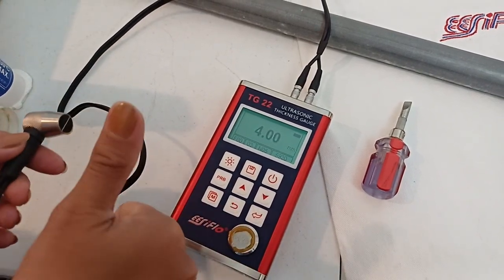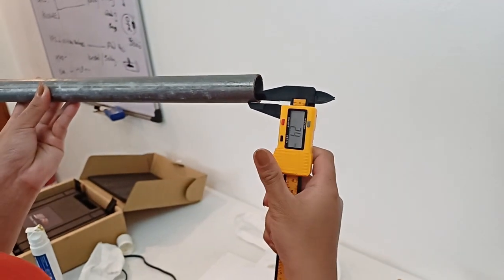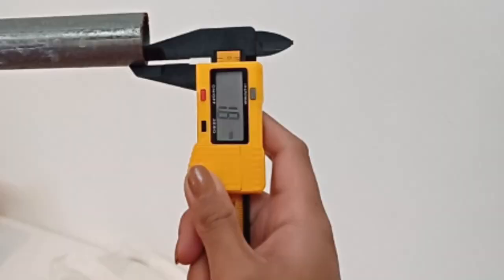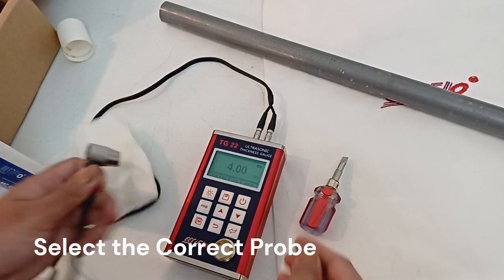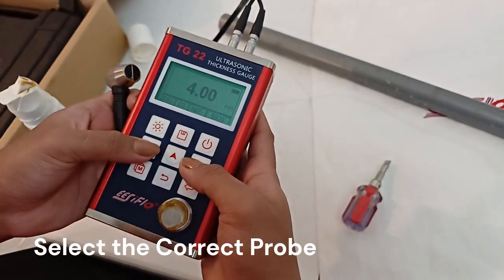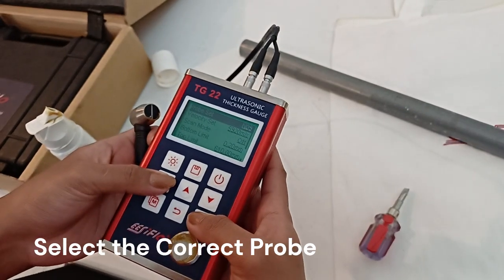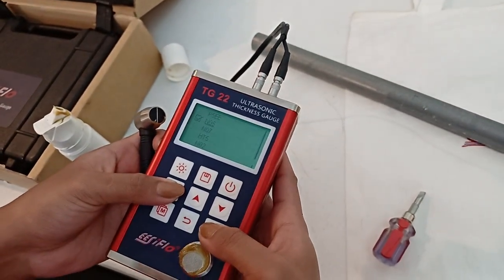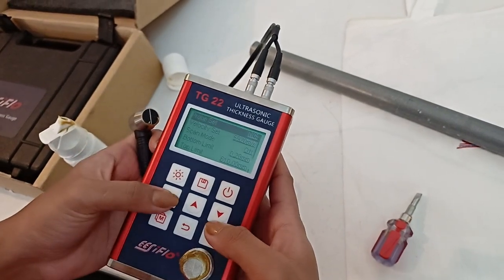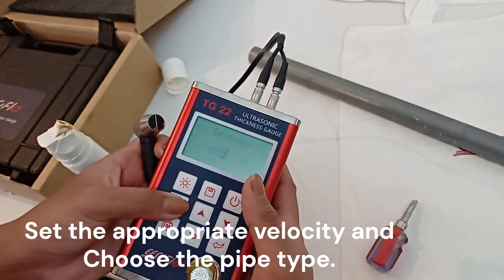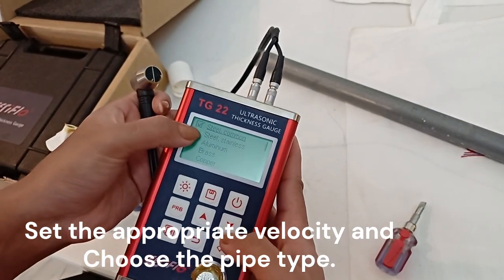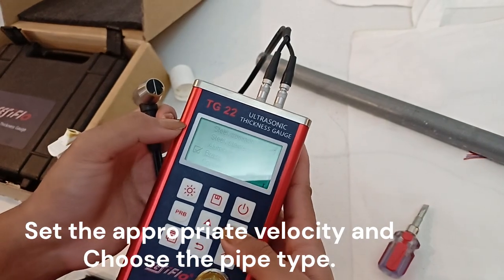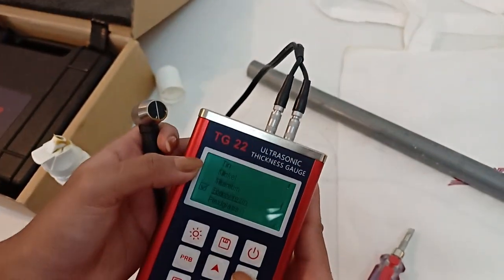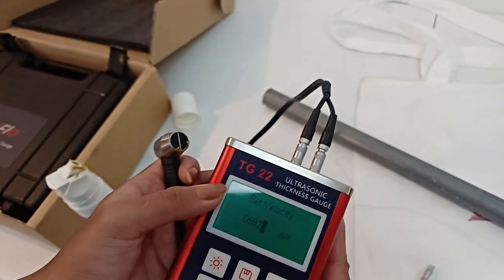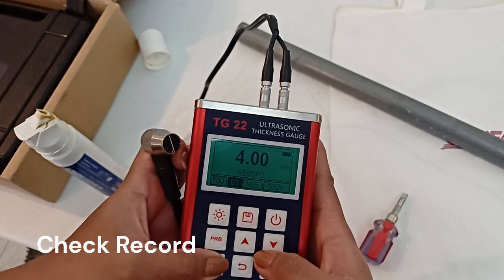To ensure the accuracy of the pipe thickness, we use a caliper first to compare the measurements with the results from the ultrasonic thickness gauge. For accurate measurements, select the correct probe. Set the appropriate velocity and choose the pipe type. Lastly, check if the settings are correct.